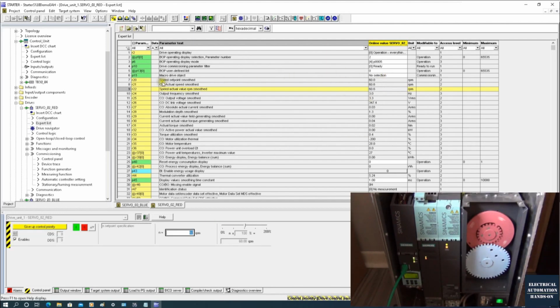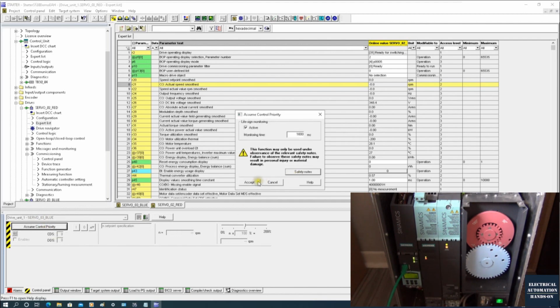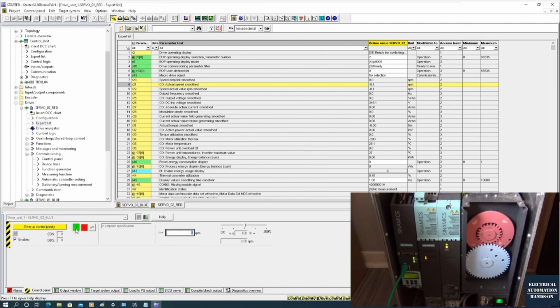So we will see set point 60, and this is the drive actual speed. And since we haven't optimized the drive yet, it shows a little bit off from our set point. That still makes sense. Okay. Stop the axis and give up this axis, and then let's shift to the blue. Make sure we named that correctly. Assume, enable, okay, and let's give minus 60. So it goes in reverse.